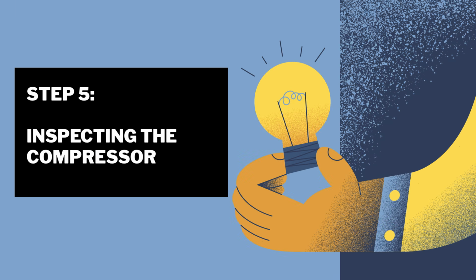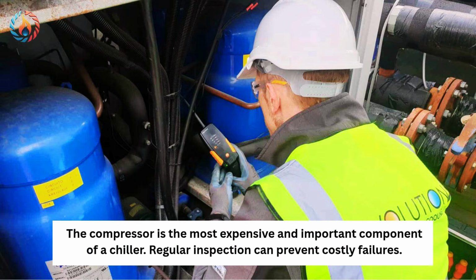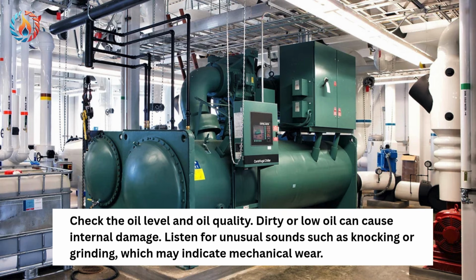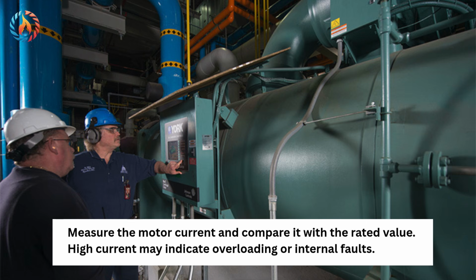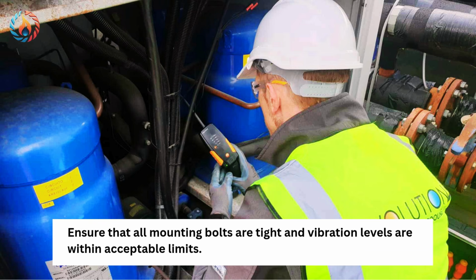Step 5. Inspecting the compressor. The compressor is the most expensive and important component of a chiller. Regular inspection can prevent costly failures. Check the oil level and oil quality. Dirty or low oil can cause internal damage. Listen for unusual sounds, such as knocking or grinding, which may indicate mechanical wear. Measure the motor current and compare it with the rated value. High current may indicate overloading or internal faults. Ensure that all mounting bolts are tight and vibration levels are within acceptable limits.